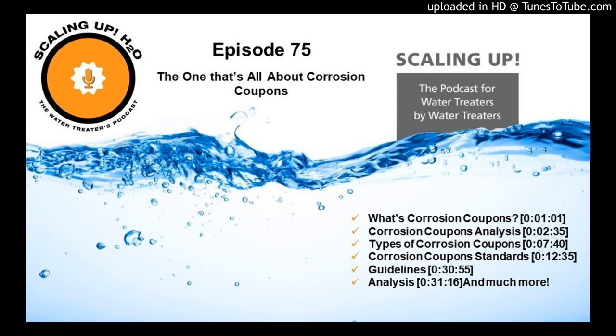So once all that is done in the lab, the person that sent it in will receive a report, and now you've got to take that to the customer and explain to them what you now know about corrosion coupons. Now, the first thing that people want to assume is that whatever corrosion has taken place on that corrosion coupon is uniform through the entire system. And folks, what I said at the top of the show, that is not true. The corrosion you are measuring is the corrosion on that coupon.